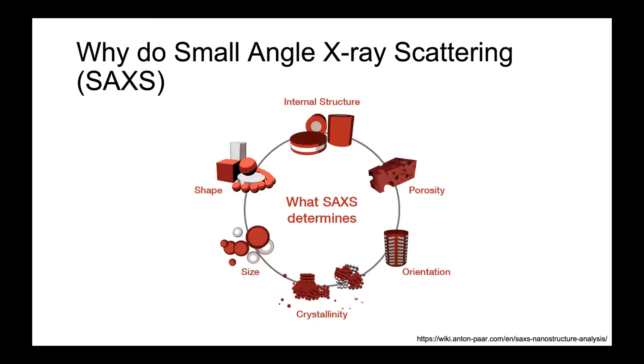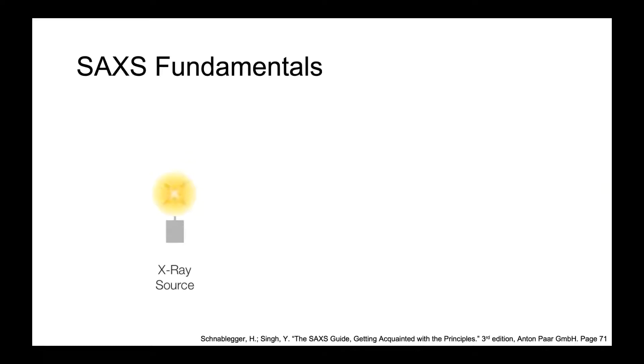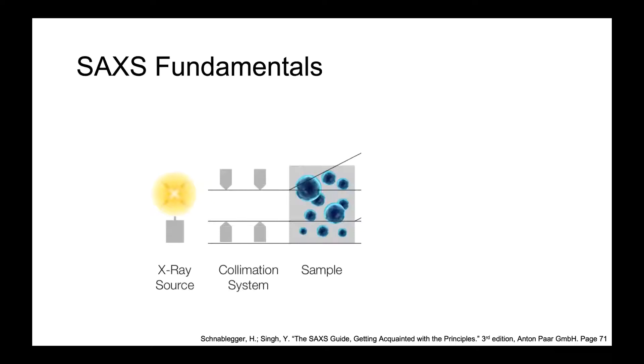Let's talk about the experimental setup. It all starts with an x-ray source — usually copper because of its longer wavelength, but molybdenum sources have also been used. Here at the MRL we use a copper source. Once those x-rays are generated, you want to get rid of divergent beams by collimating them, which makes the beam more uniform and the experiment more accurate. Those x-rays then exit the collimator and irradiate your sample, where elastic scattering occurs.